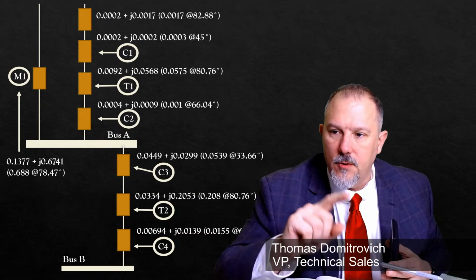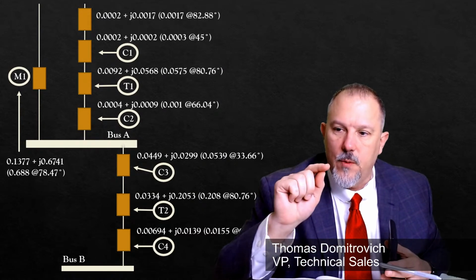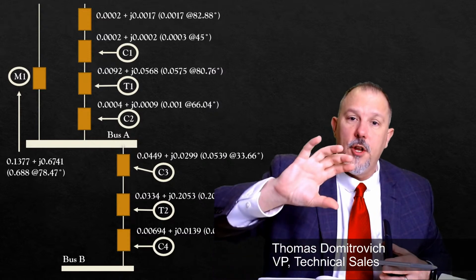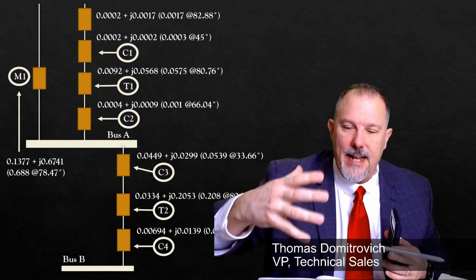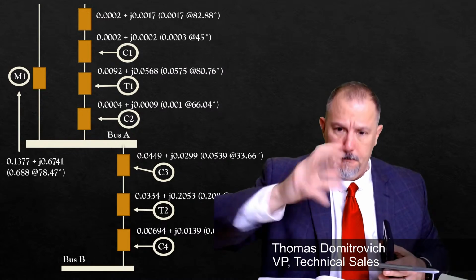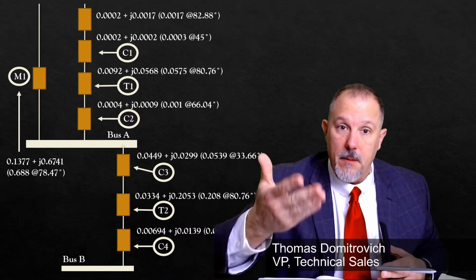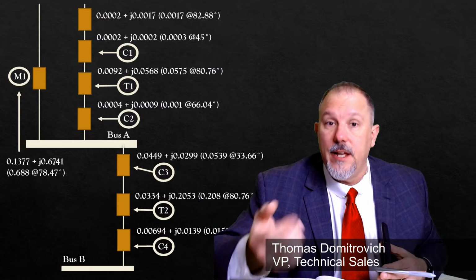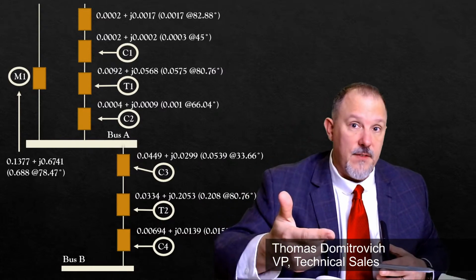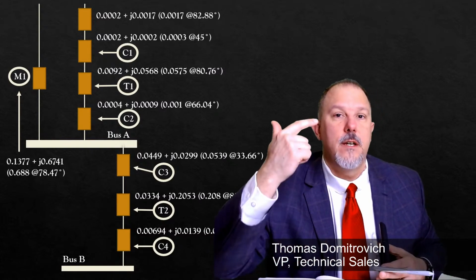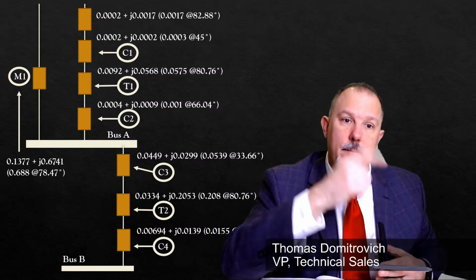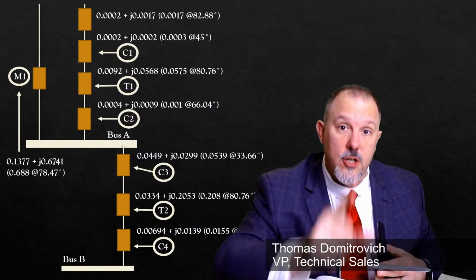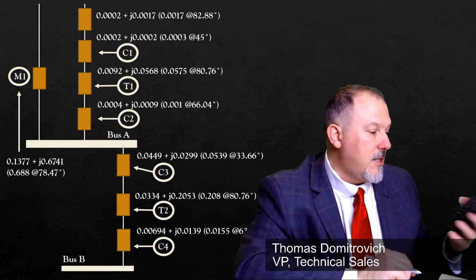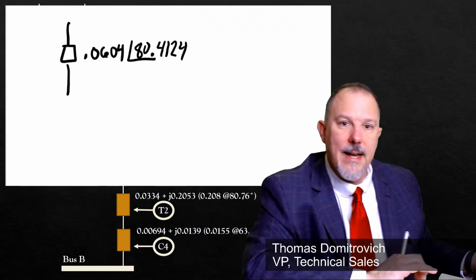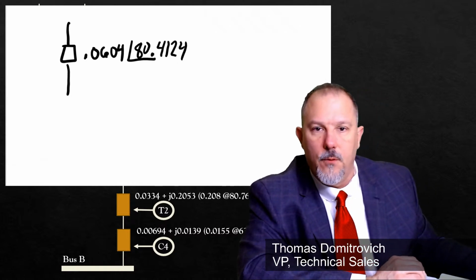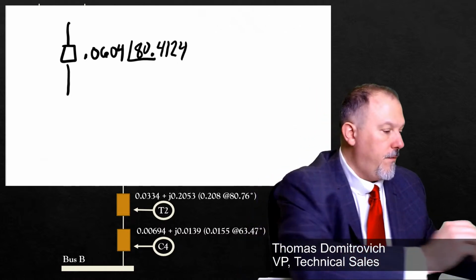So Robert, a motor turns into a generator when a fault condition occurs, when the field collapses. That's exactly right. What do you have? You have the rotor turning. You have the stator standing still. That rotor turns into a generator, but it won't generate zero sequence currents. It will generate positive and negative sequence currents. So we model that motor in the positive and negative sequence circuits, but we don't include it in the zero sequence circuit. So what I got is 0.0604 at an angle of 80.4124.